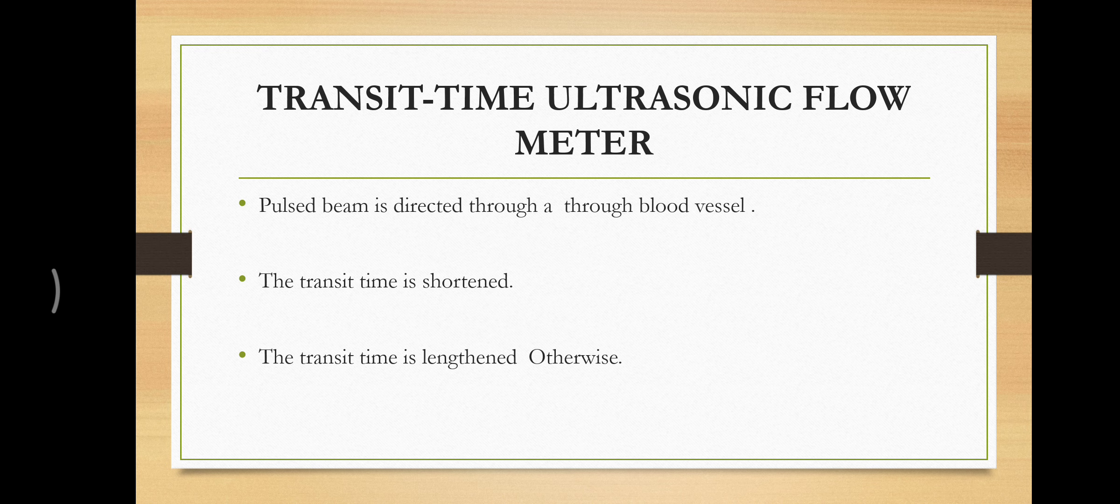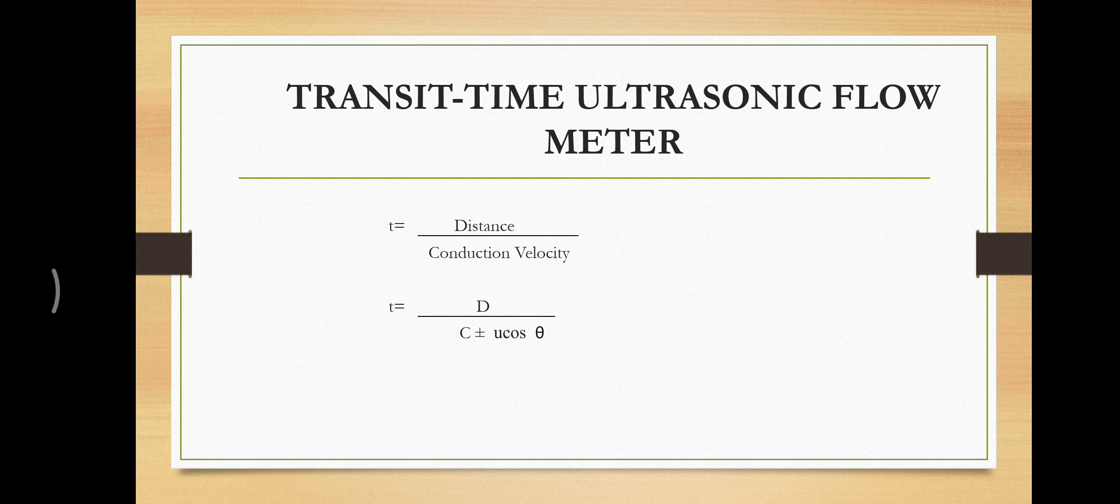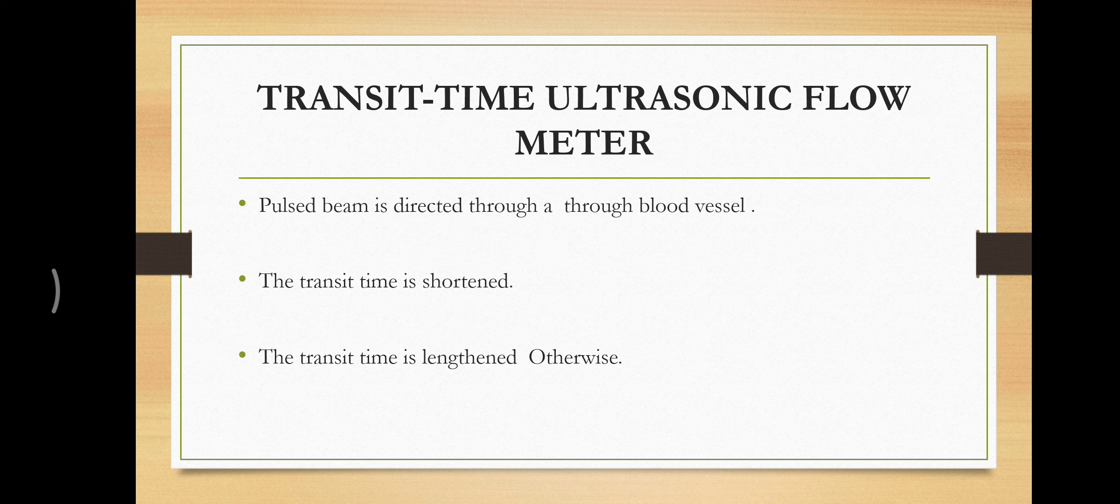Transit time ultrasonic flow meter. The two transducers are placed in blood vessels and the transmit times are calculated by using this formula. The transit time is shortened when the blood flows in the same direction as the transmitted energy, but the transmit time is lengthened when the blood flows in the opposite direction as the transmitted energy.